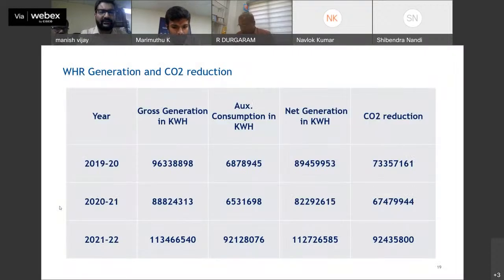Last but not least, I would like to conclude that the designing of the WHR is an essential or critical factor for generation of the power. Before designing the boiler, you should know how much heat is required for drying the raw mill. If you know the exact amount required, then we will be able to ascertain the temperature drop across the boiler, and the boiler should be designed accordingly.